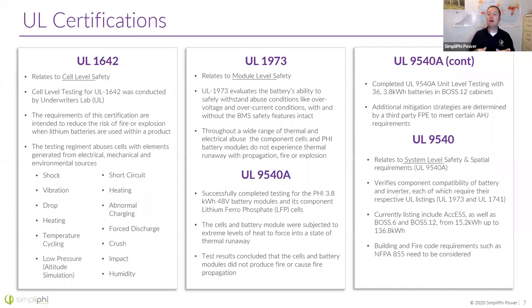So what those tests show us in the 9540A dictate what the 9540A testing standard will be. When we think about NFPA 855, it says you've got to have 3 feet between batteries, you can only have a certain number of kilowatt hours in a certain location, you have to have X, Y, and Z. Well, what we can do is show with a 9540A, which dictates our 9540 UL listing, that we can circumnavigate or supersede some of those NFPA 855 rules.